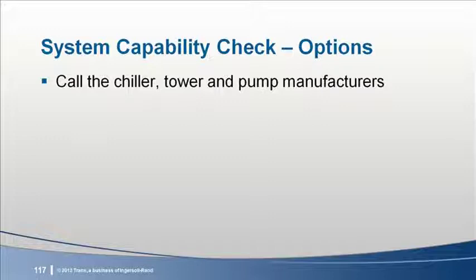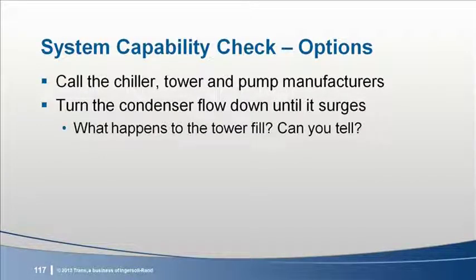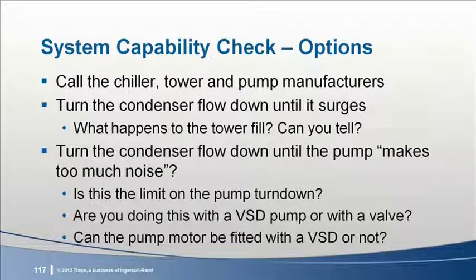The other thing you may have going for you on an existing chiller plant is that you don't have to wonder about actual system limits. You have equipment there that can help you find the limits in reality rather than theory. For example, turn the condenser flow down until the chiller starts to approach surge. This would be the stall region, which does not harm the chiller, but it does start to make noises you're hopefully not accustomed to. The less noticeable effect would be in tower performance. Is the fill starting to get dry in spots? Is there a flow when the tower performance starts to drop off noticeably? And what about the limits on the condenser pump? If you already have a variable speed drive on the pump or a throttling valve, what happens when you turn it down?